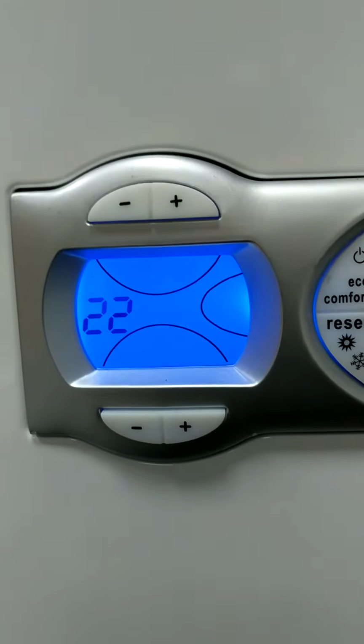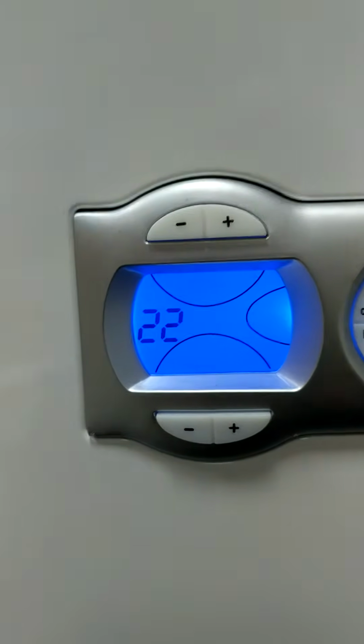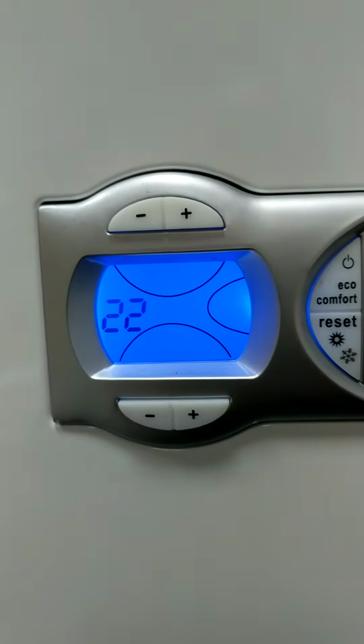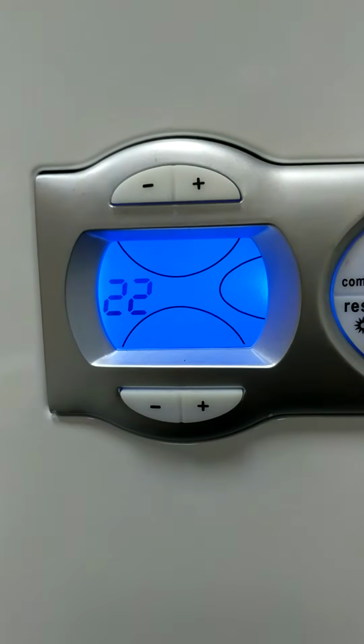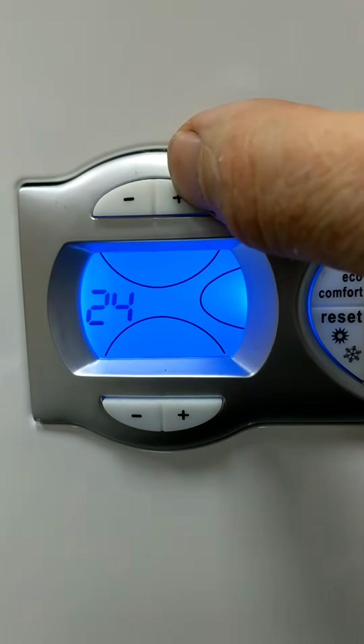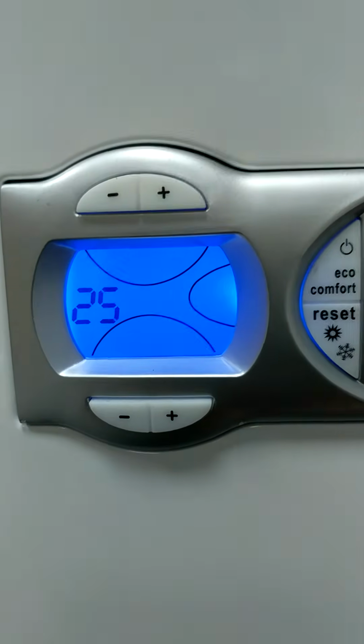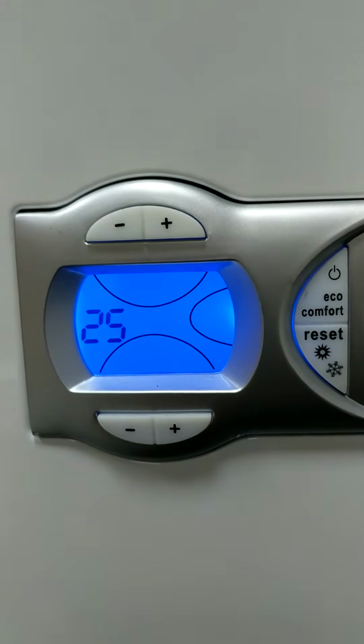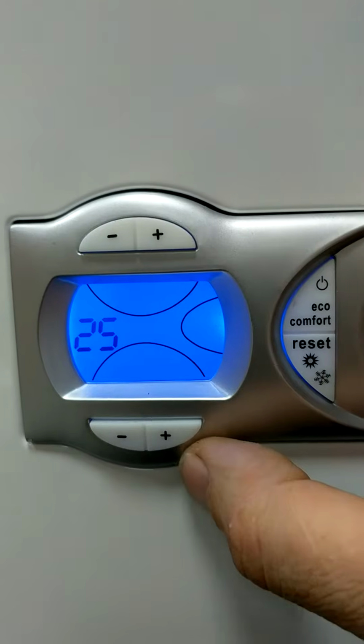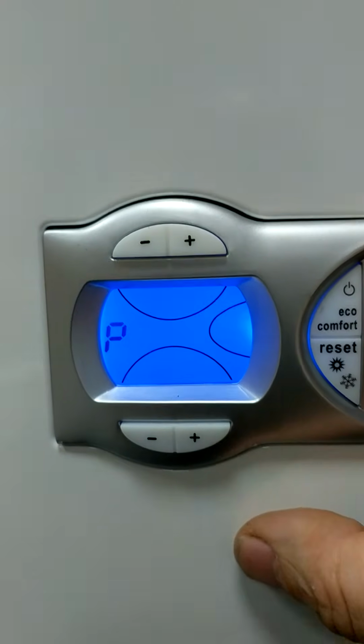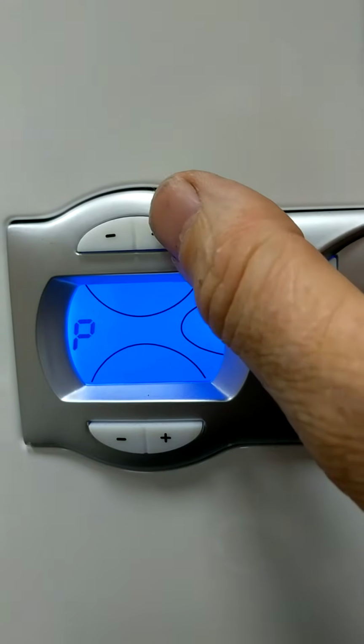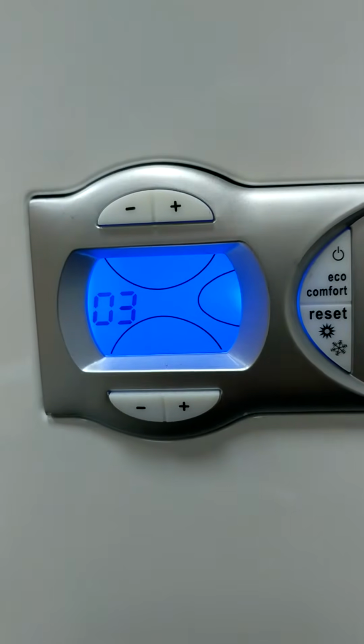If you have a listen or watch the burners, you'll actually hear how well it lights up. If it comes on with a bang, lower it down. If it's not quite lighting across, then just increase it. Okay, so that's the ignition pressure, parameter 1. Then you're going to go to the ramp rate. So we press the bottom plus button to change the parameter, and the top plus button to see its value.